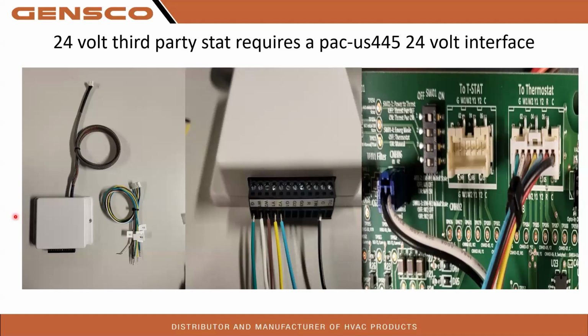So yes, PAC 445, this is it right here. This is the 24-volt interface you would need for the IntelliHeat coil in order to run a 24-volt thermostat. Same interface as all of our other equipment. So if you have SVZs, PEADs, all that kind of stuff, same interface. This pigtail that comes with the 445 is for the PAA coil. Most guys just end up throwing this away because your SVZs and your PEADs do not require this.